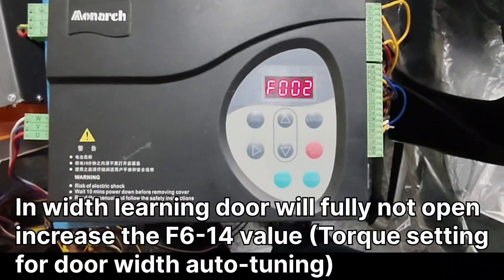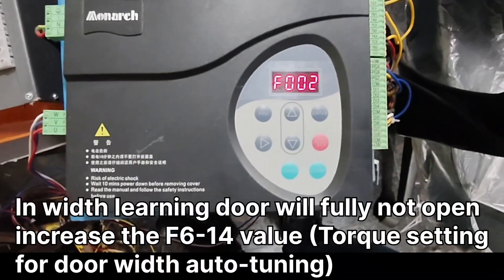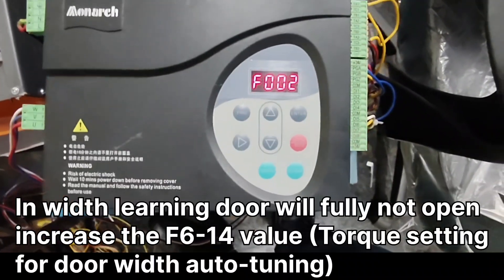In width learning time, if door does not fully open, increase the F614 opening torque value.